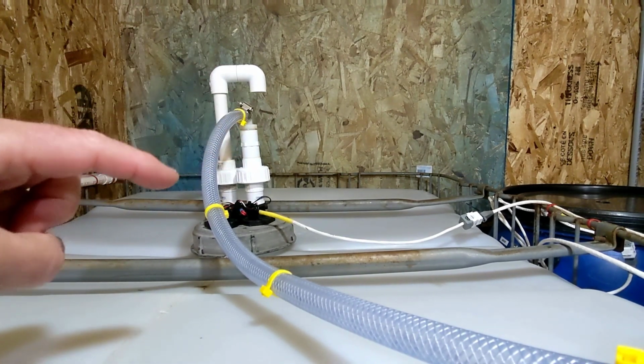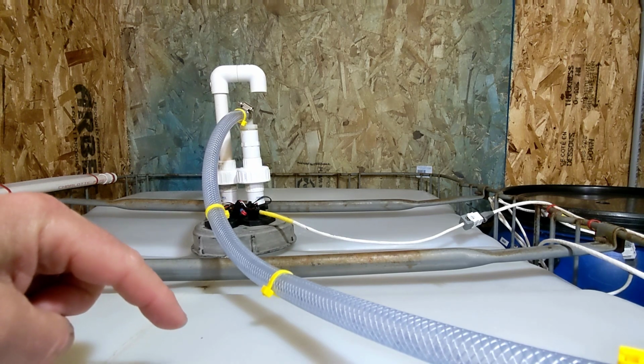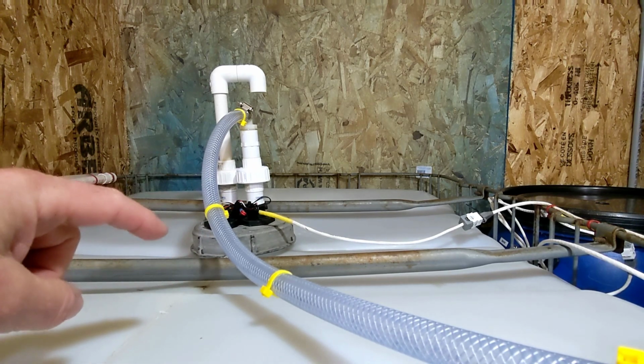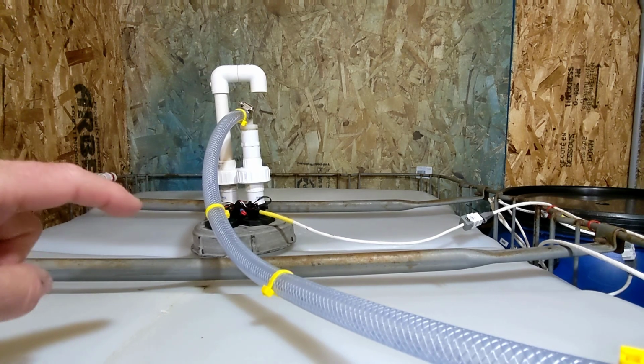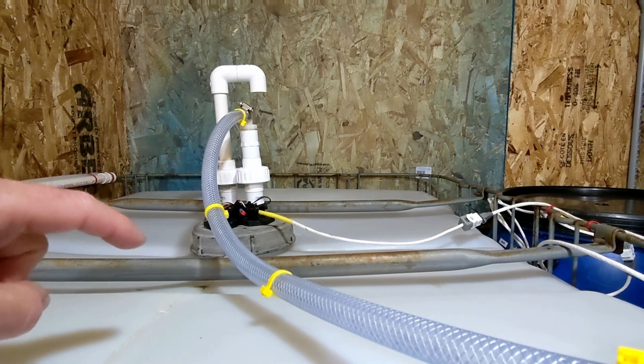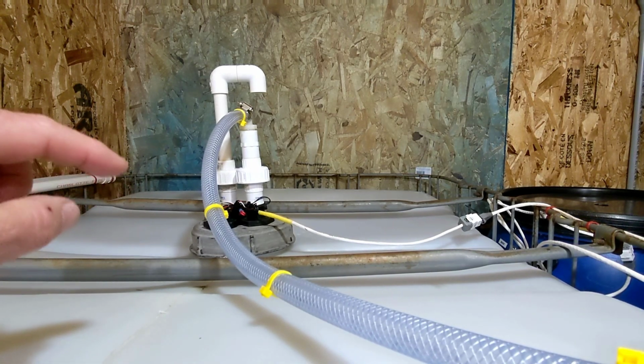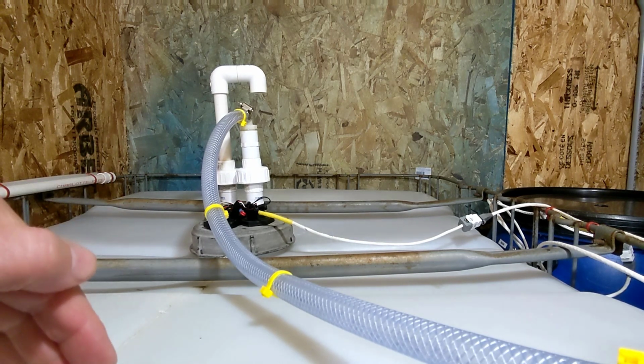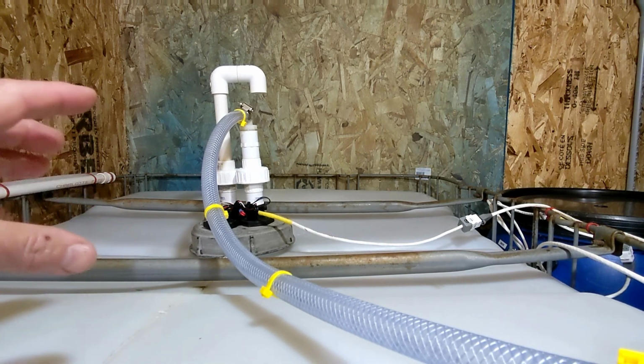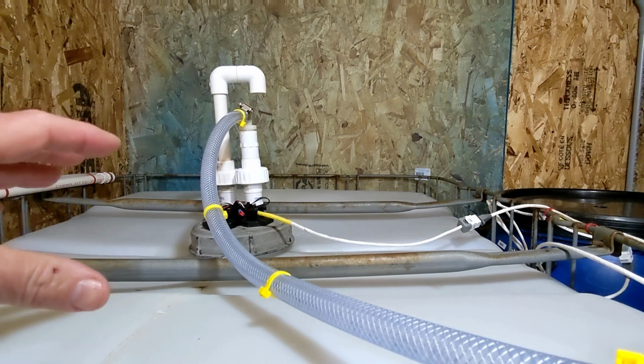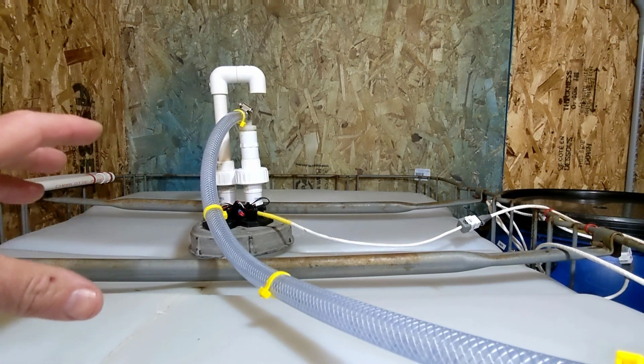And then I have a stem that has a float switch on it, the two float switches, one at the bottom and the one at the top. And it also has a laser rangefinder on it, an infrared laser rangefinder that can tell me the exact distance down to the surface of the sap to the millimeter. So I can look on the control panel in my office and see how much sap is in the tote.